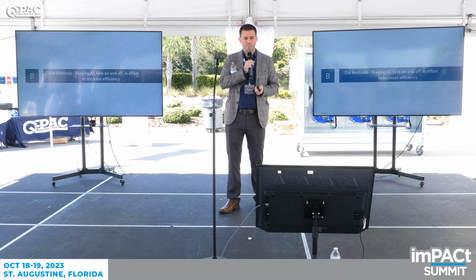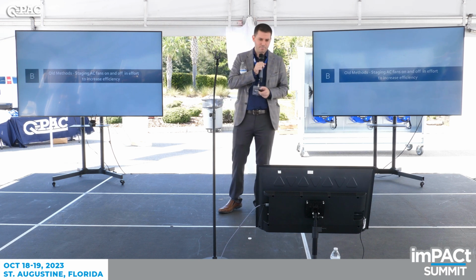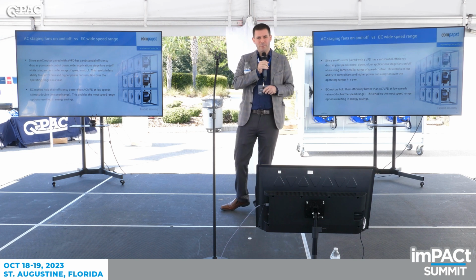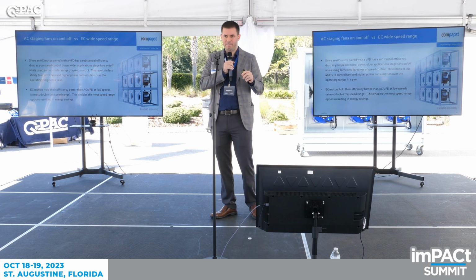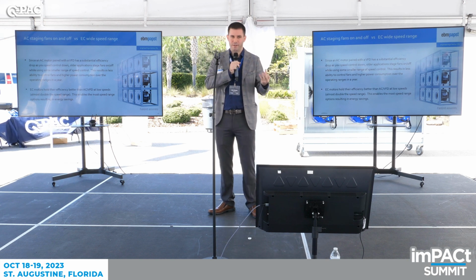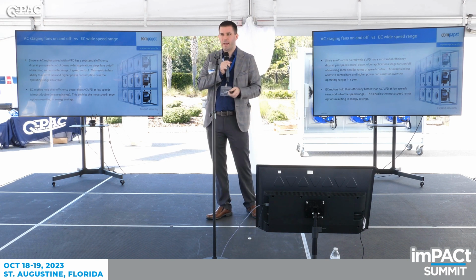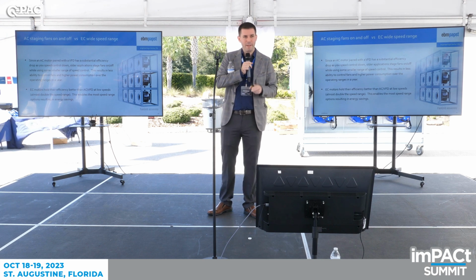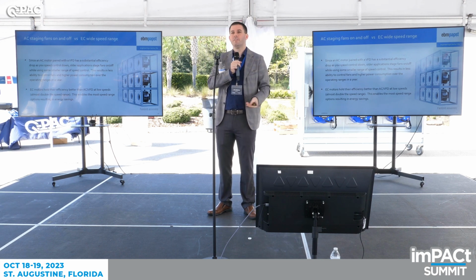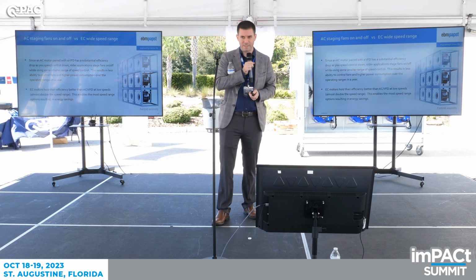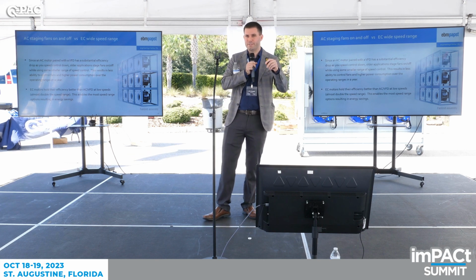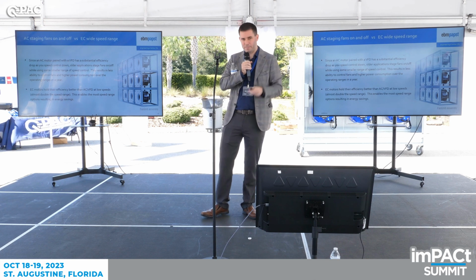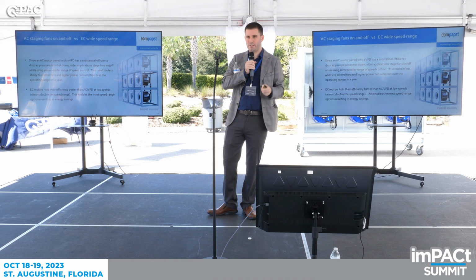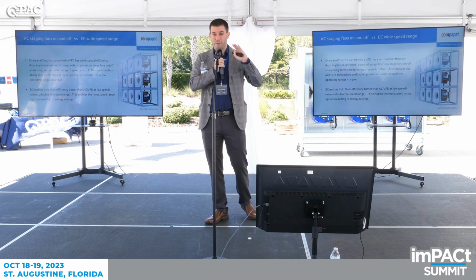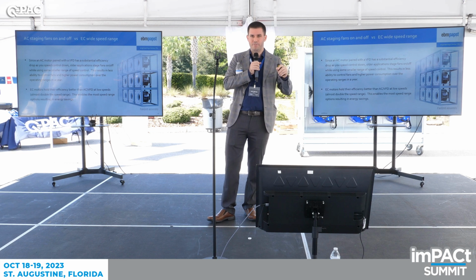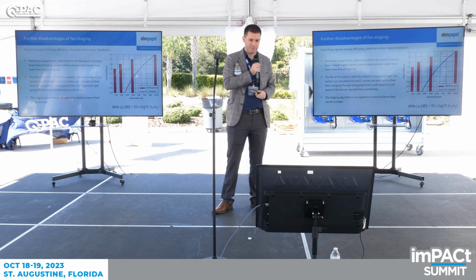And then there's the method of, instead of speed control, staging fans on and off. One thing I want to say is I talked about how power is cubic to the speed of the fan, which means excess power is going into the bearings as heat, and that's going to shorten the life of your product. So if you could speed control the fan down a little bit, the life actually goes up exponentially. So when you're turning fans on and off, say you wanted 50% airflow and you turned off half the fans, the rest are going to be running at 100% speed. You're actually going to be drawing more power, getting shorter lifetime of those fans, and it's going to be noisier. So this kind of shows it a little bit.